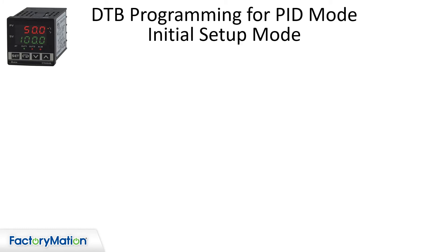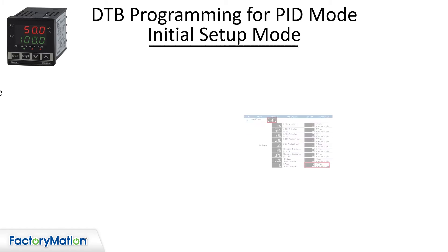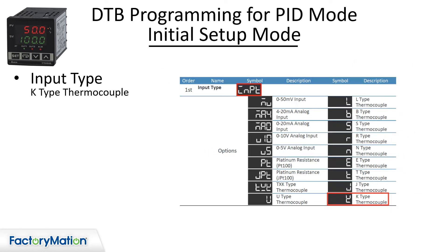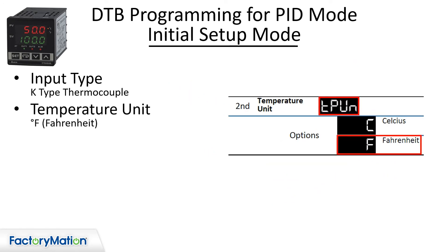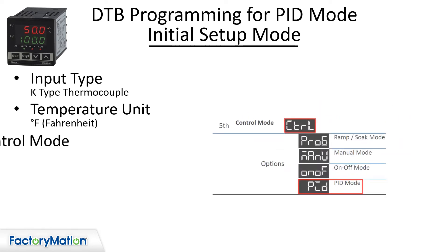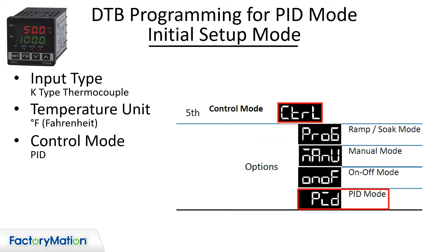To program the DTB for PID control, go to the initial setup mode. Set the input for K-type thermocouple. Set the temperature units to Fahrenheit. Set the control mode to PID.